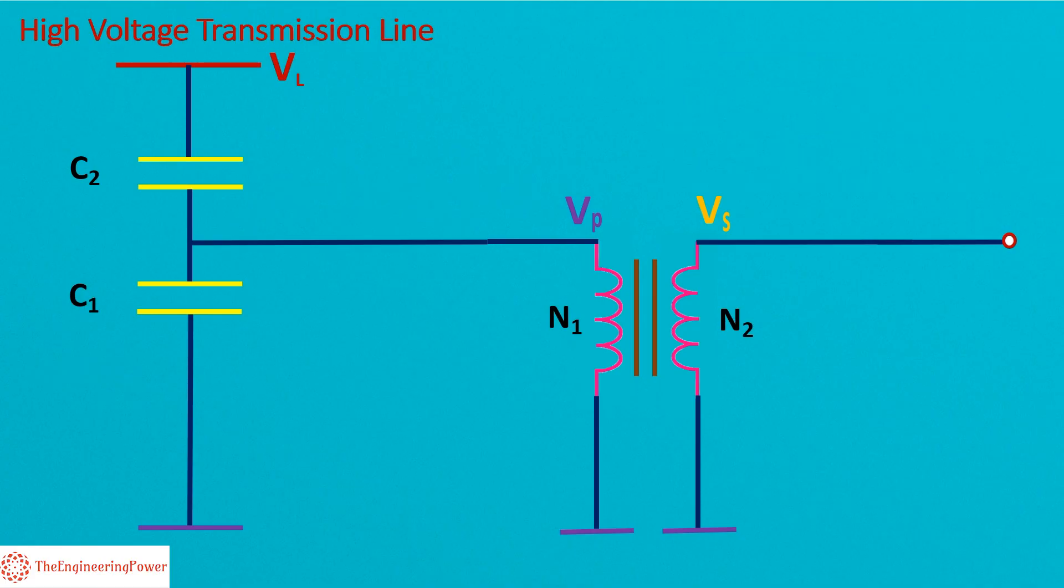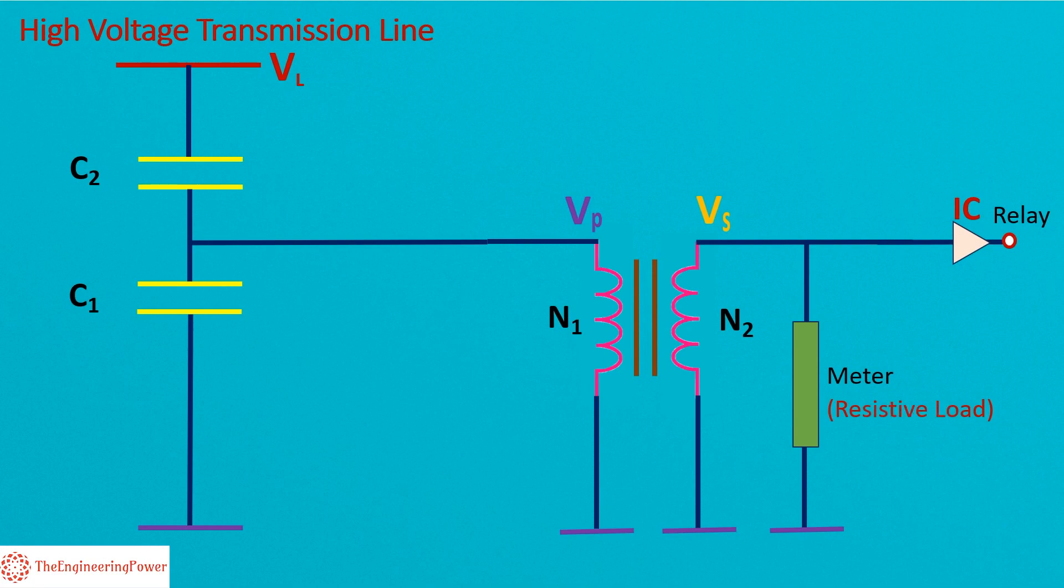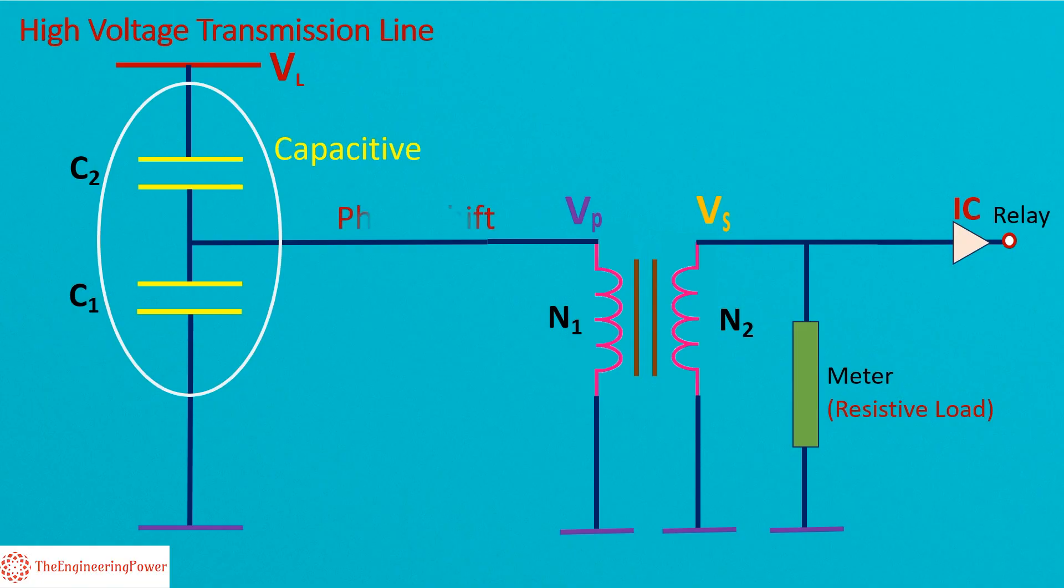The output voltage of the CVT, Vs, is either fed to a meter or relay. It's directly fed to the meter. However, for protection and control purposes, the voltage is first fed to an IC which is programmed according to the requirements, and output of this IC is then fed to relays. But here, meter will be a resistive load whereas the potential divider is capacitive. Therefore there will be a phase shift which will affect the output voltage. To solve this problem, an inductor is placed in series with the auxiliary transformer. This inductor with inductance L will compensate the effect of capacitive phase shift.